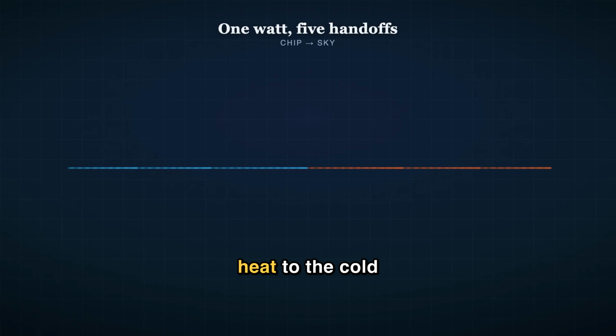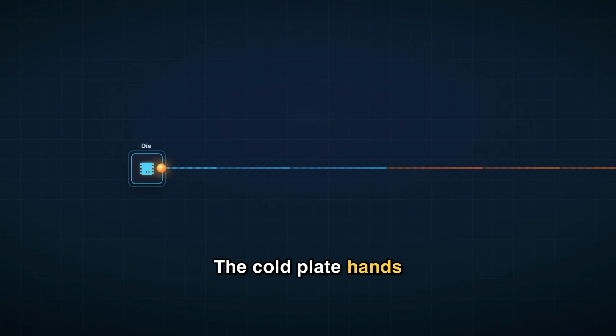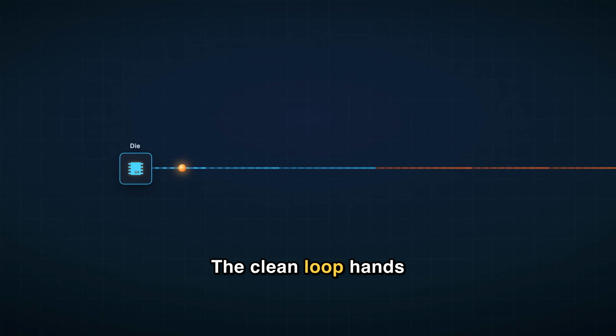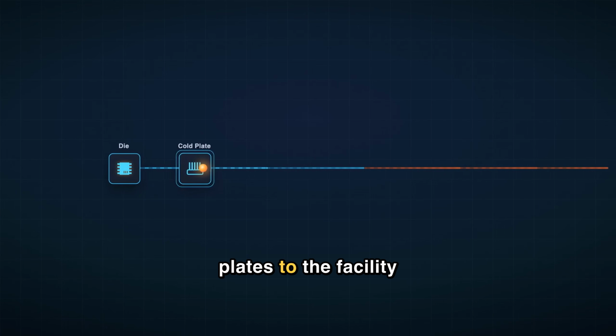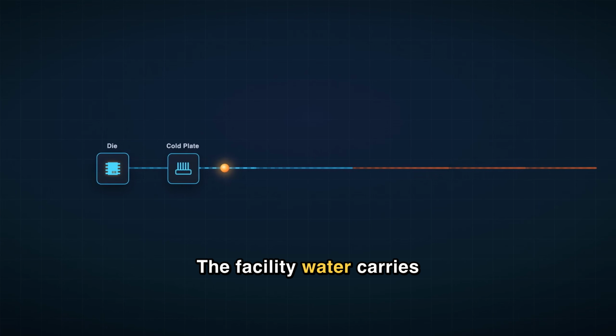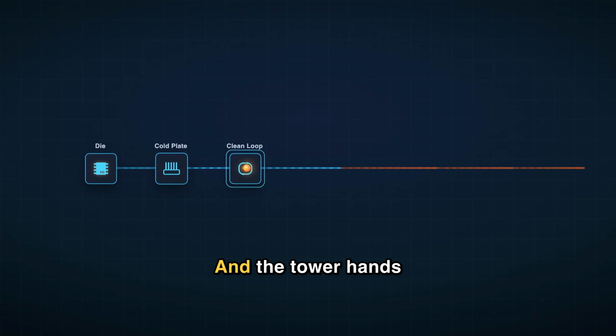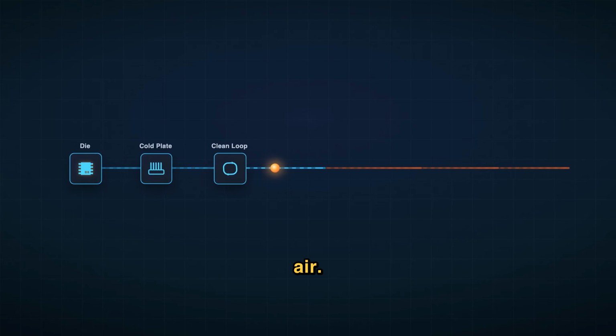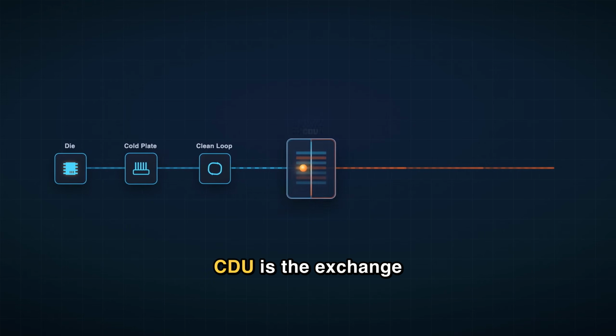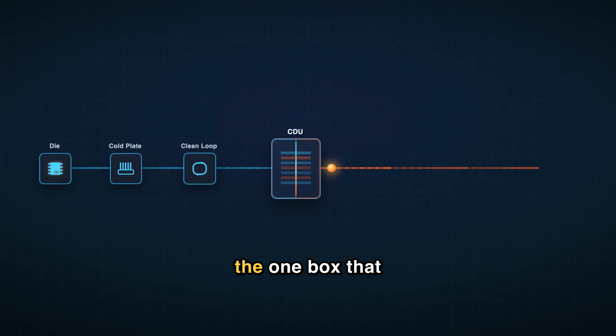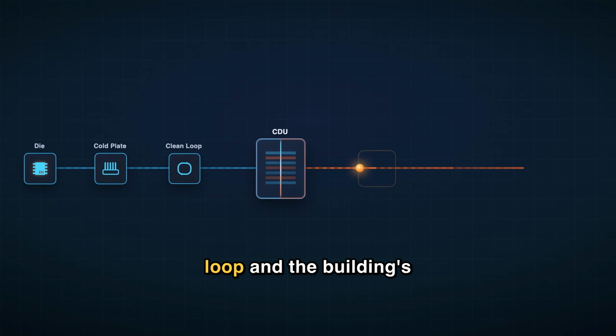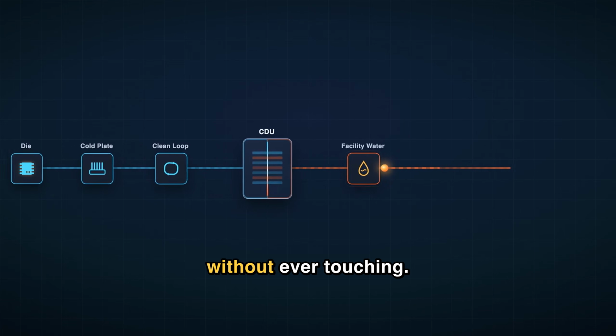So there's the whole relay in one breath. The die hands its heat to the cold plate. The cold plate hands it to the clean chip loop. The clean loop hands it across the CDU's plates to the facility water. The facility water carries it to the cooling tower. And the tower hands it to the open air. 5 handoffs, and the CDU is the exchange point in the middle.